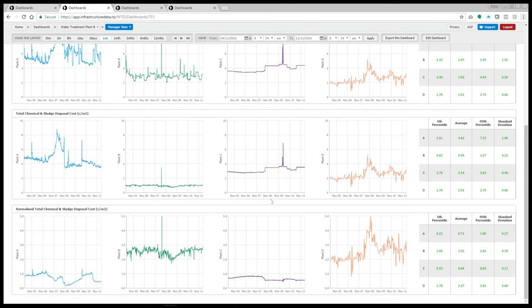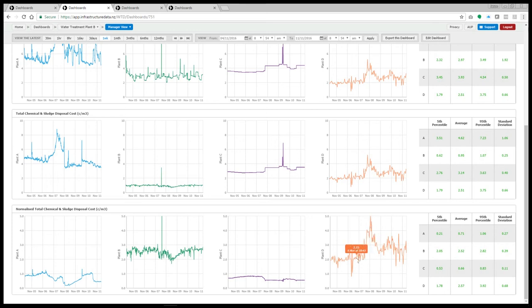So in order to compare apples with apples, we need to normalize for source water quality. Once we've done that, some interesting insights start to show themselves. In this example, plants A, C and D are all treating similar river water qualities, and yet plant D is significantly higher cost. This suggests there are some operating inefficiencies on plant D, and investigating those could potentially realize some operational savings.